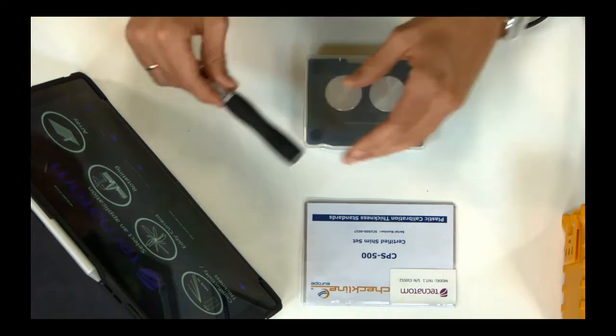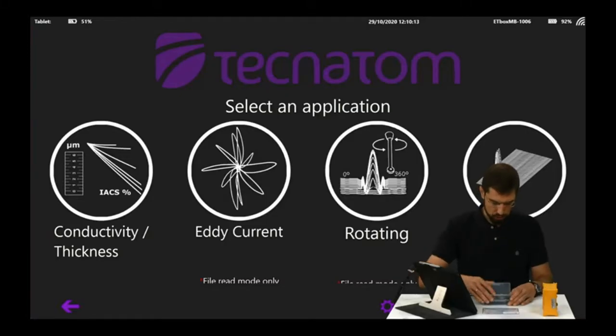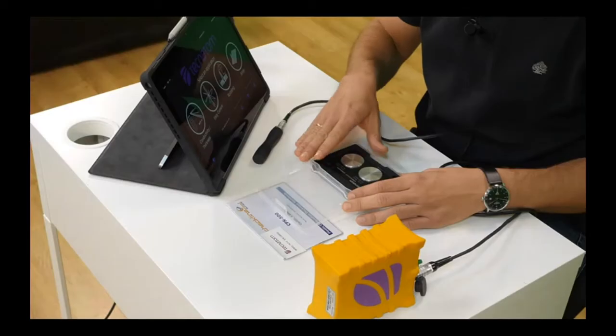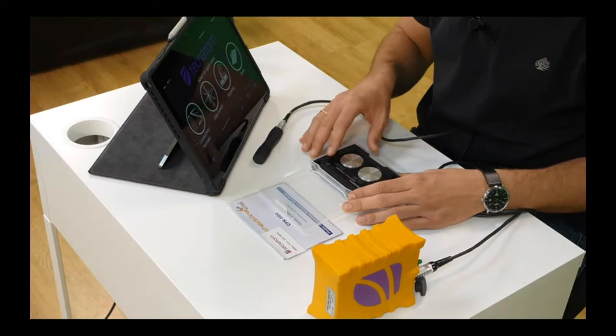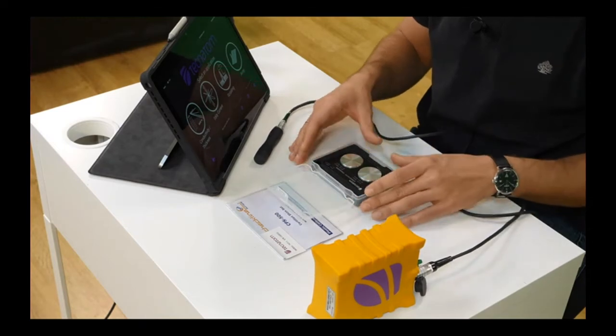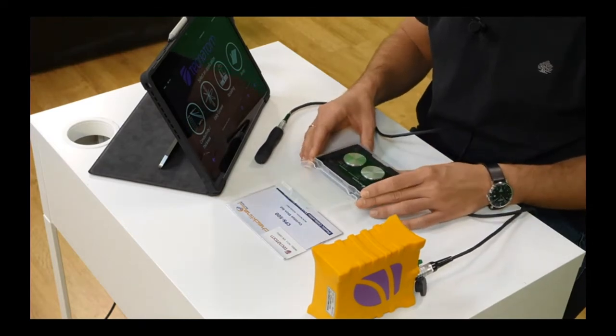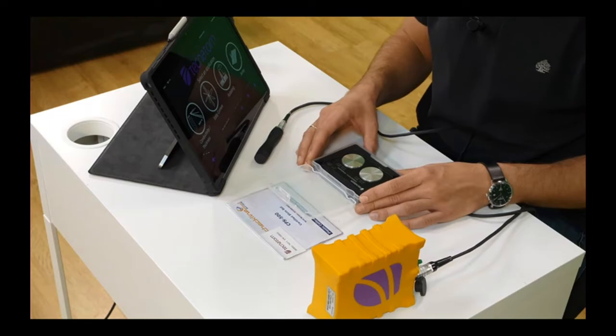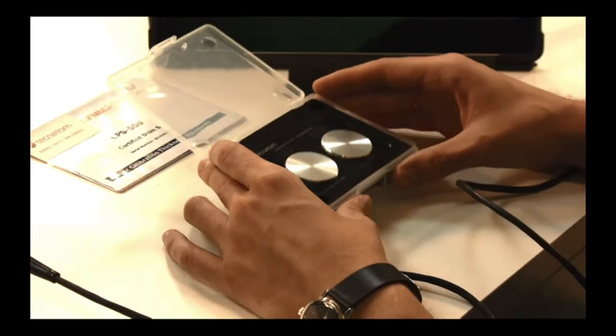For this demonstration, we also have two conductivity measuring blocks. In this case, these are two aluminum blocks that have their own certificate. These blocks are manufactured and certified by Tecnatom to calibrate the conductivity test.